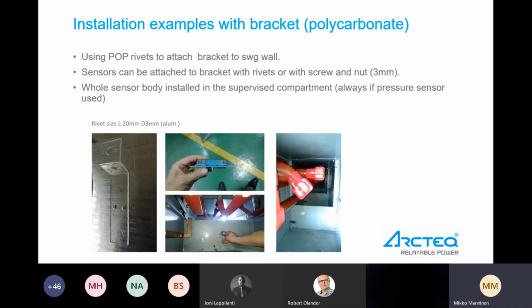There are a lot of moving parts, and one important thing is that all the switchboards have some levels of insulation, and the point sensors should not disturb those insulation levels. So if at some point there is for example a 20 centimeter minimum distance, we should not put the sensor closer than 20 centimeters. But that is more like a common sense rule, that the switchgear should have the same insulation level as before the retrofit of this arc flash protection.